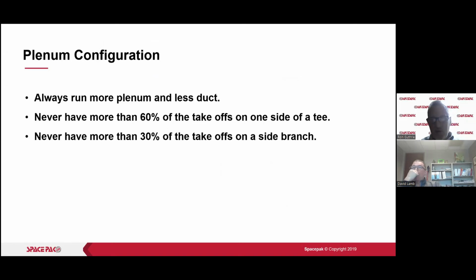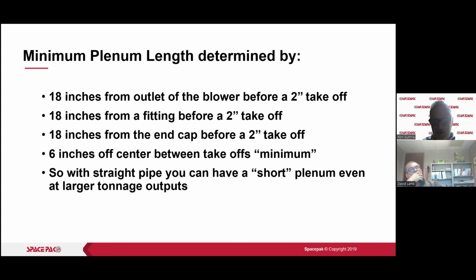Again, always run more plenum and less duct. Never have more than 60% of the takeoffs on one side of a T. That's the 60-40 rule, 50-50 to 60-40. Never have more than 30% of the takeoffs on the side branch. We can have less, but not more than that.